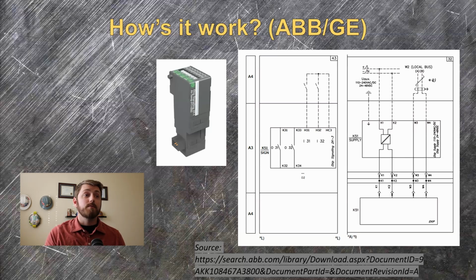You have to be careful with this because you can totally screw up the wiring, accidentally or maliciously, to make the light come on without having the breaker in maintenance mode. A system can be designed where multiple breakers are put into maintenance mode at the same time from one switch. For those, any indication feedback should be wired in series so that all of the breakers have to be enabled in maintenance mode for that LED to turn on. If you do it any other way, really you're doing it wrong, unless they're coming out of a communication module that sends the maintenance mode signal out to each breaker. We'll talk about those more in a second.